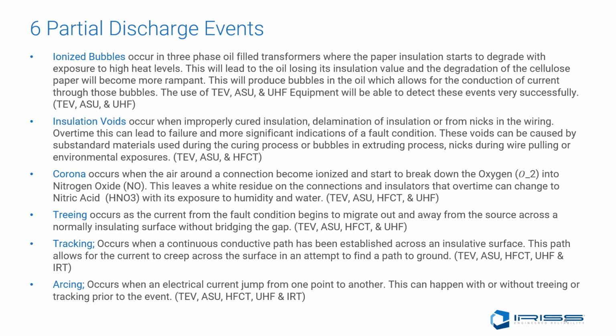Treeing occurs as the current from the fault condition begins to migrate out and away from the source across a normally insulated surface without bridging the gap. This will be detectable using TEV and ASU devices. Tracking occurs when a continuous conductive path has been established across an insulative surface. This path allows for the current to creep across the surface in an attempt to find a path to ground. This will produce TEV, ASU, and infrared indications.